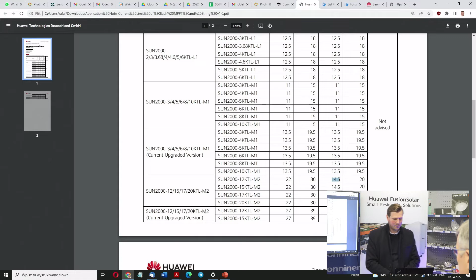On each input of the Huawei inverter there's a current sensor measuring the current independently. So if it measures that you're reaching the point of 14.5, it will not allow more current inside - you won't be able to go above this value. So if you connect two strings in parallel, it means you will potentially lose about 40% of your power.